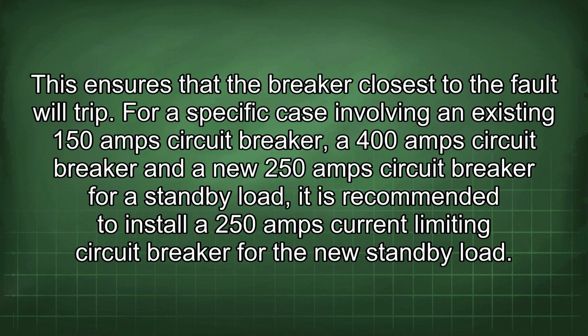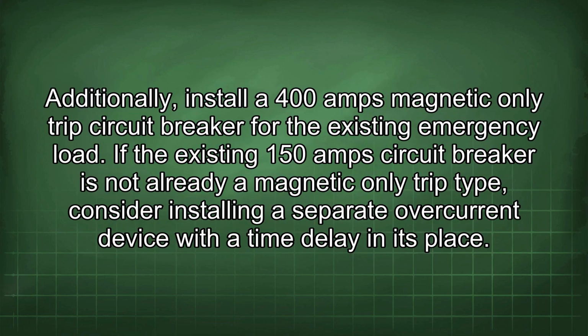For a specific case involving an existing 150 amp circuit breaker, a 400 amp circuit breaker, and a new 250 amp circuit breaker for a standby load, it is recommended to install a 250 amp current-limiting circuit breaker for the new standby load. Additionally, install a 400 amp magnetic-only trip circuit breaker for the existing emergency load. If the existing 150 amp circuit breaker is not already a magnetic-only trip type, consider installing a separate overcurrent device with a time delay in its place.